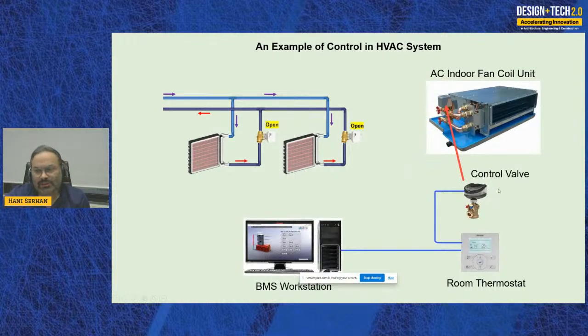But over time, with technology evolution, we now have actuators that can open the valve just the portion required to air condition the room. So for example, if we're looking for a temperature of 24 degrees, and the room is at 28, the thermostat will command the actuator to open fully. Now, when it starts dropping from 28 to 27, the thermostat will request the actuator to close by 25%. So the closer the actual temperature of the room gets to the setting point, the more flow throttling will occur on the valve. So this is part of the energy saving in modern buildings.